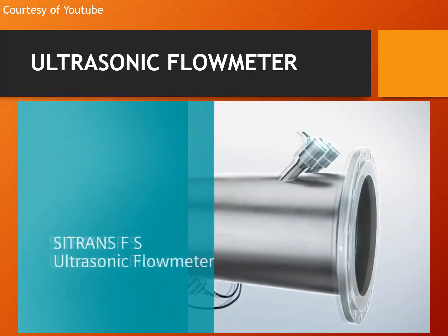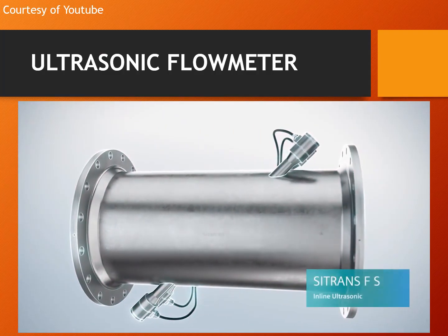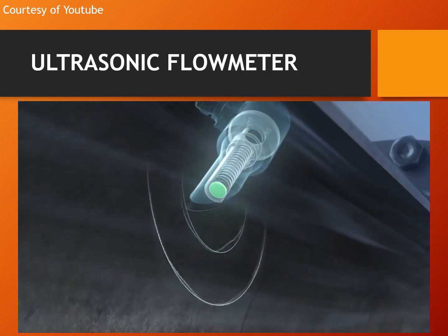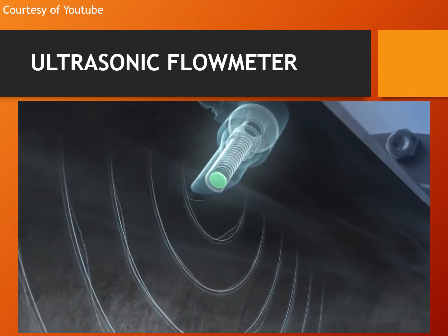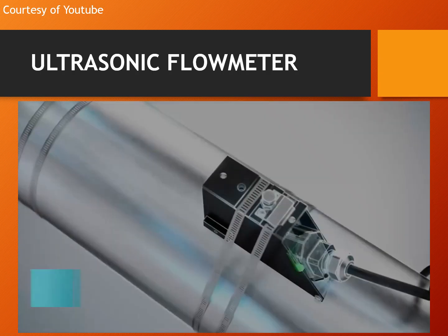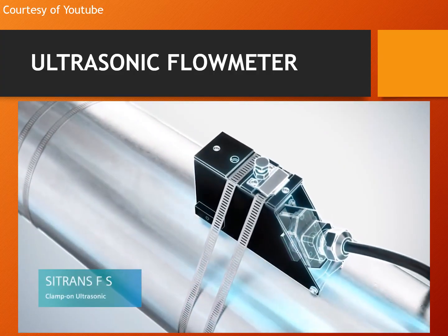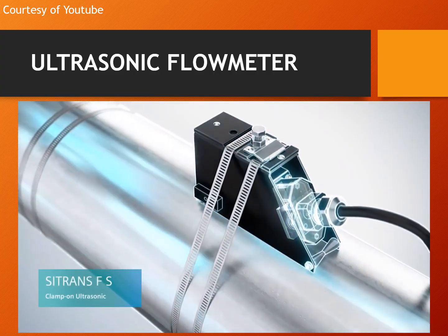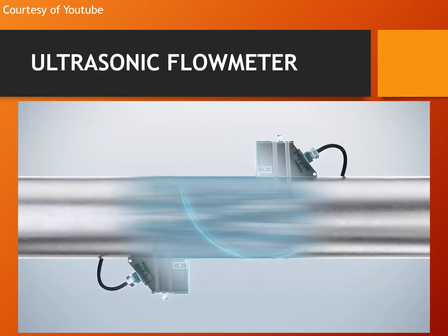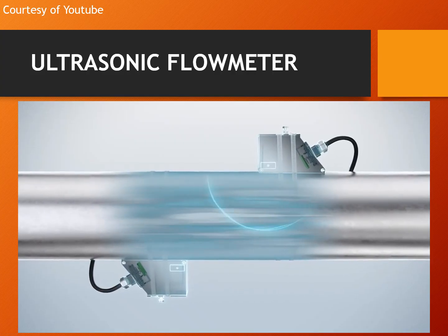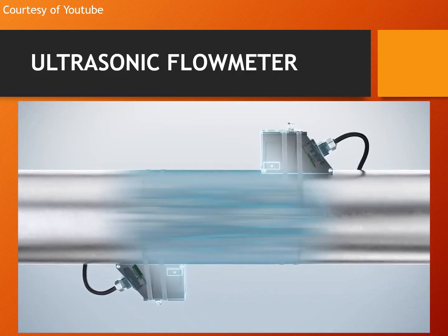The inline product family measures with very high accuracy. The sensors are in direct contact with the medium. The clamp-on version, however, uses sensors that are mounted on the outside of the pipe. Ongoing processes are not interrupted and the sensors never touch the medium.